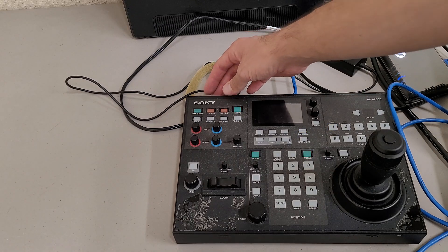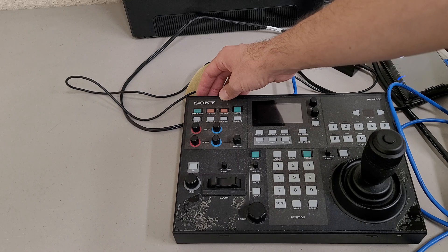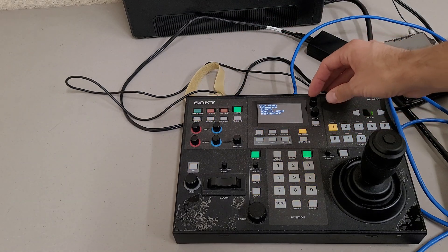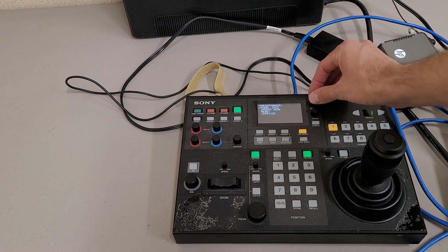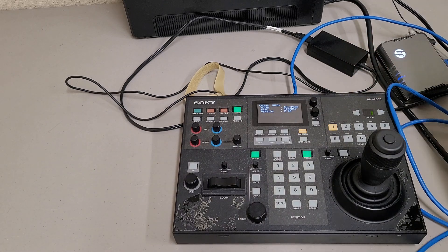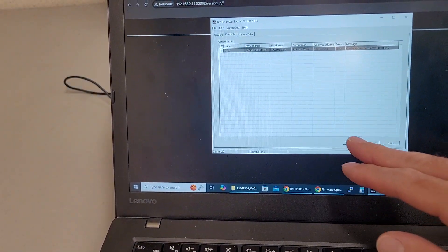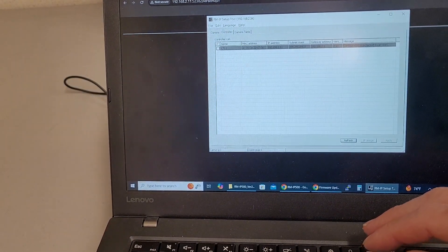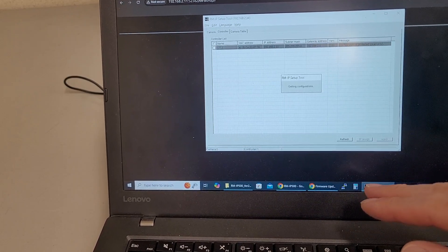Now I'm going to power cycle the unit. Cross all my fingers and toes — and boom, still works! Going back to maintenance, model info — the firmware stuck. Click refresh. Configuration is still protected and it doesn't show the right version. Interesting.